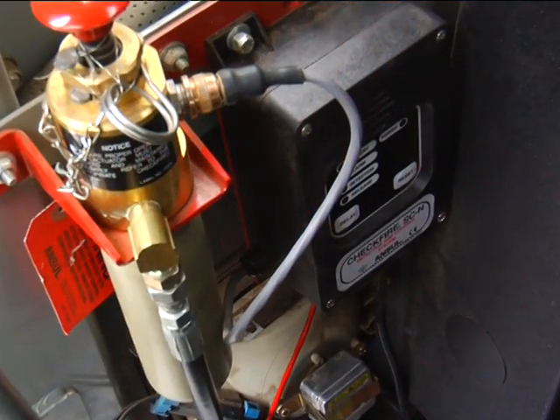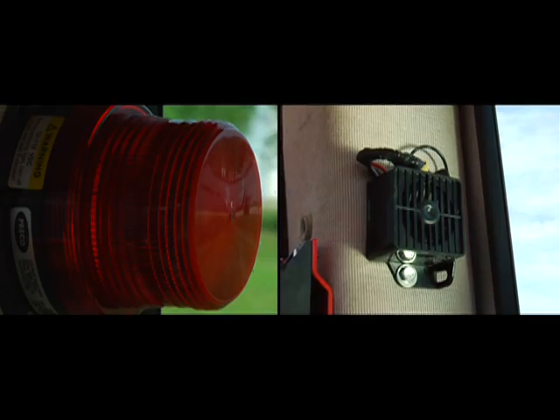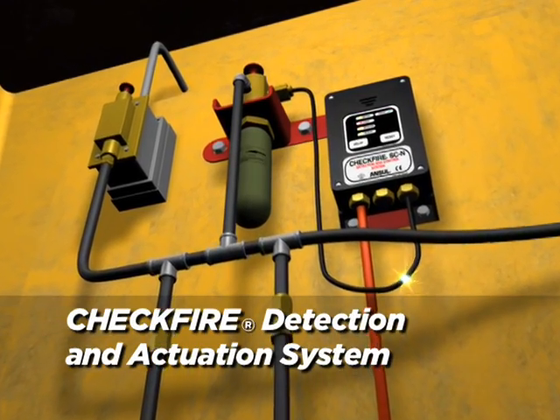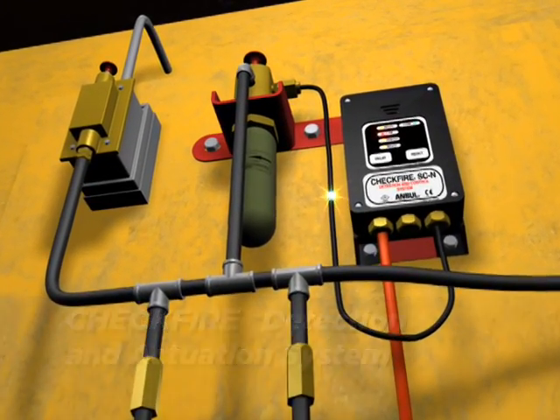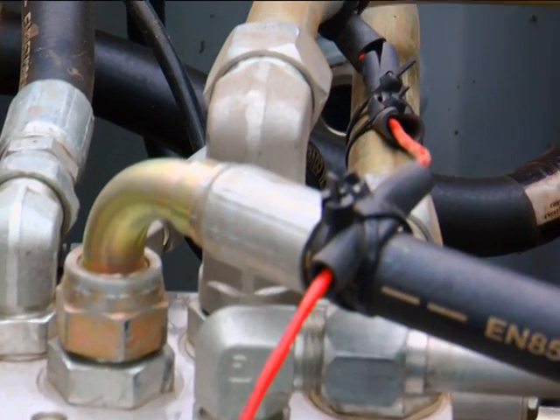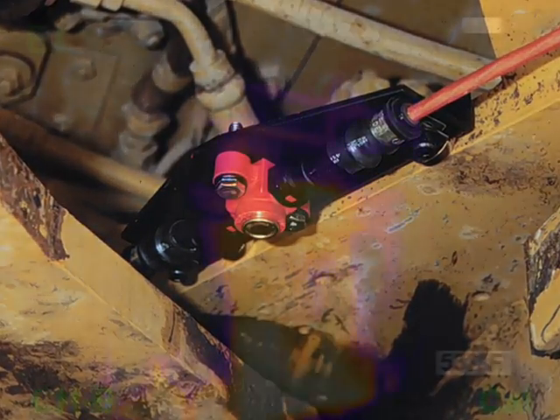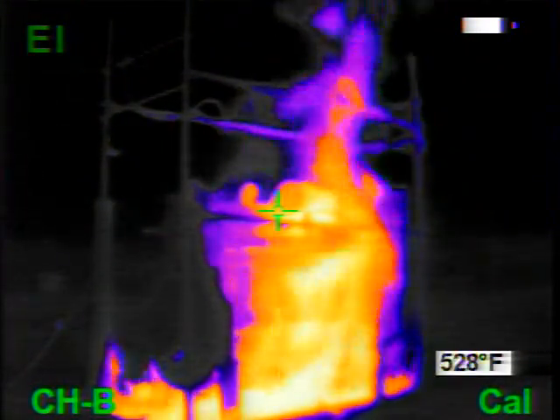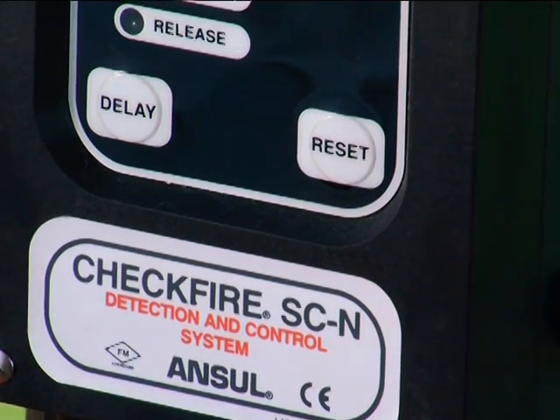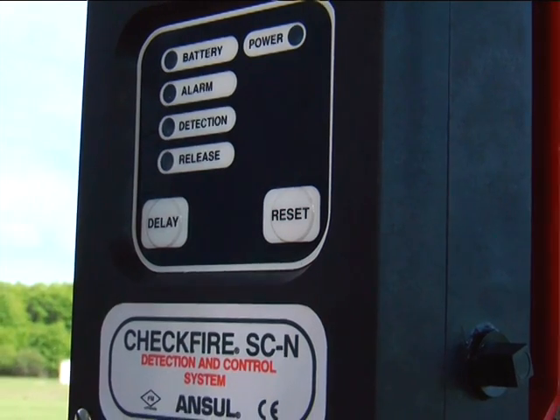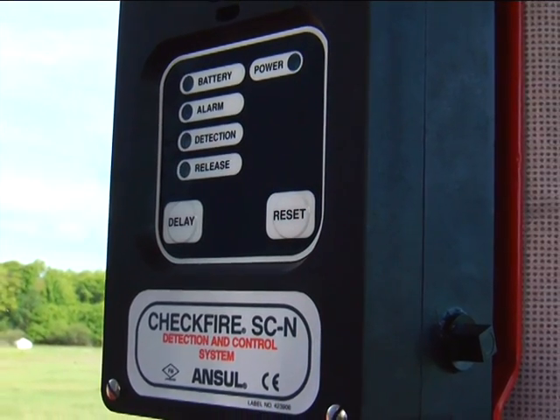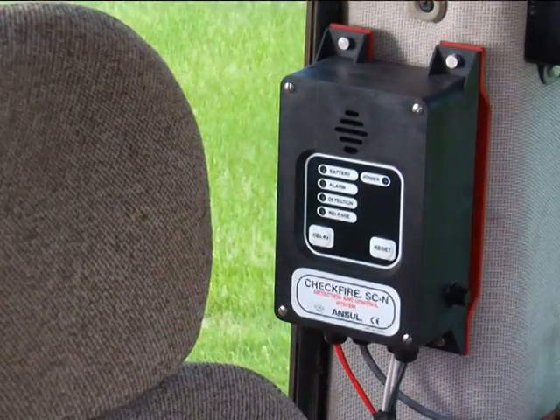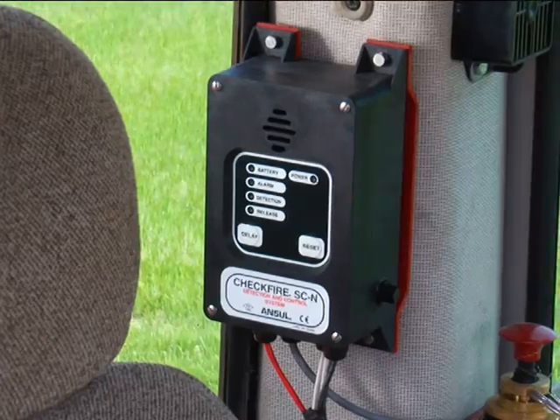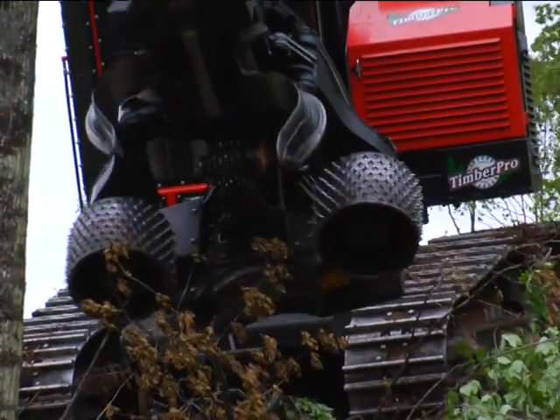The Ansul Mobile Equipment Fire Suppression Solution starts with fire detection. Ansul's Check Fire Detection and Control Actuation System provides rapid activation and deployment of the fire suppression system. The system may have thermal linear detection wire, thermal spot detectors, infrared, or all three, depending upon the configuration of the equipment. The Check Fire SCN, or self-contained model, provides automatic fire detection, equipment shutdown, and fire suppression system actuation. With its environmentally sealed control module, the Check Fire SCN system resists shock and excessive vibration. It has self-checking diagnostics and a completely self-contained power source for the ultimate reliability in the most difficult conditions.